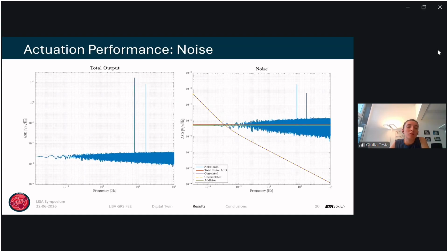This is what the amplitude spectral densities look like in this case when injecting all 3 noise contributions to the simulation. On the left-hand side, we have the plot of the total output, showing very strong resonances at the frequencies we were considering for the specific commands, and down here the shape of the noise. We've isolated the noise on the right-hand side, and as you can see, it again follows very well the model given by the red line, a model that is actually dominated by the additive noise contribution, which is why it looks pretty flat.